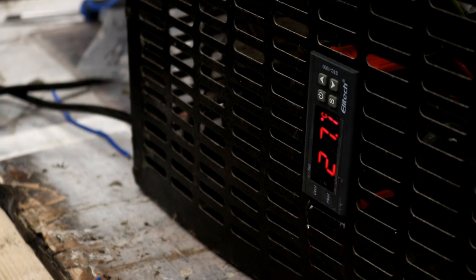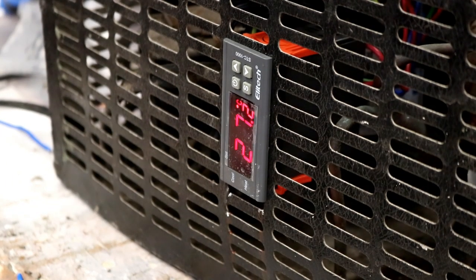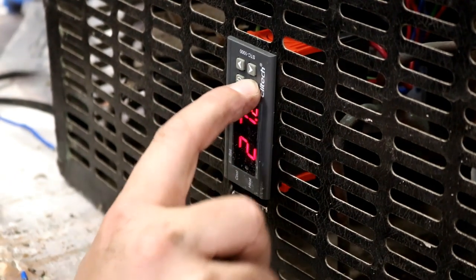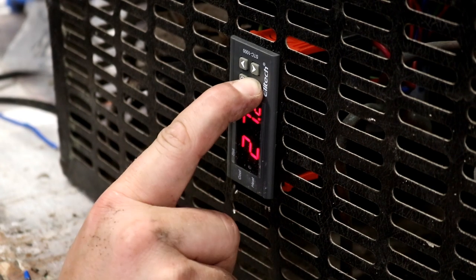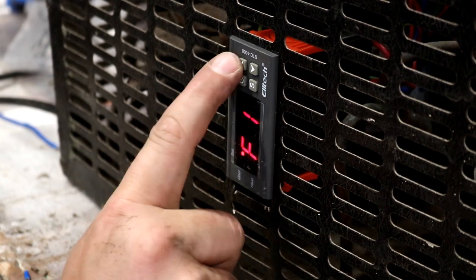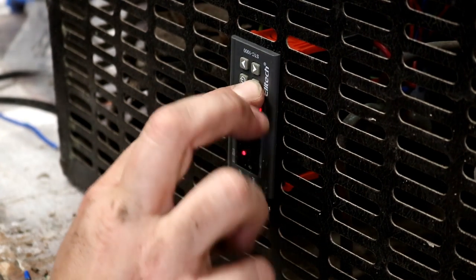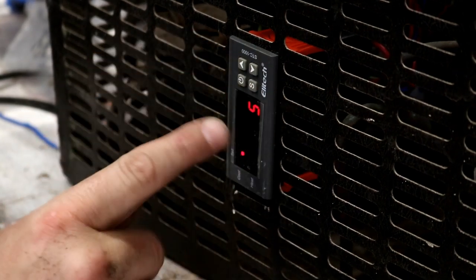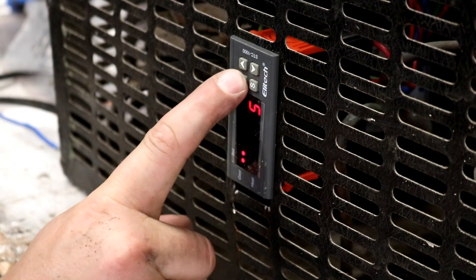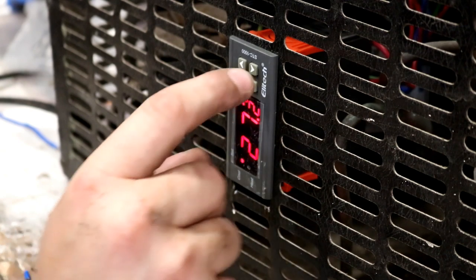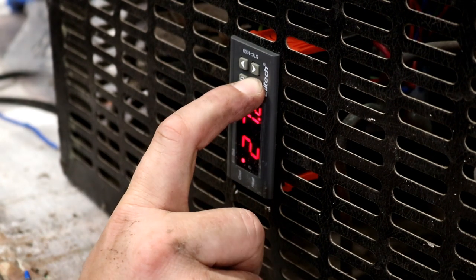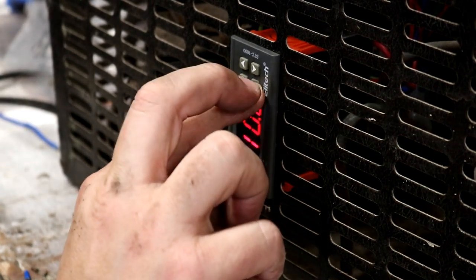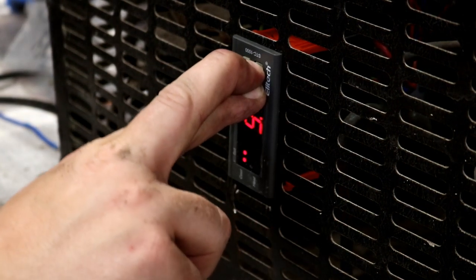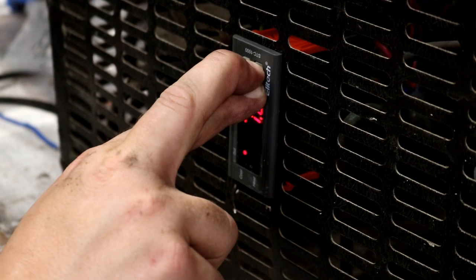So what I like to do now, just so we're prepared for the next time we turn this machine on, I'll press and hold the set button, go up to F3, and turn the pump delay to 5 minutes. We'll press the start button to lock that in, then press and hold the set button again, and under F1 press the set button to scroll down to a negative temperature.